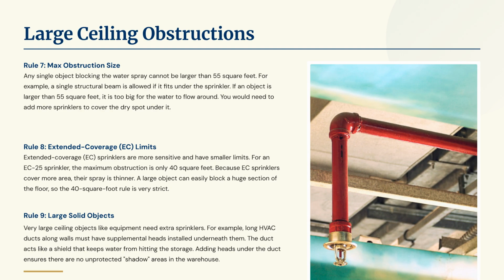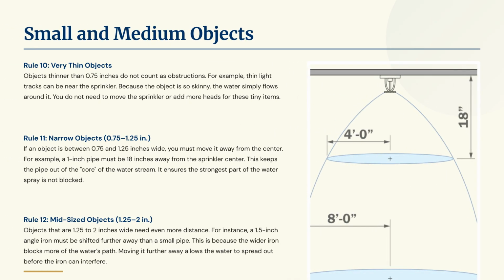Rule 9 requires supplemental heads under large solid objects, like HVAC ducts, to prevent shadowed areas. Rule 10 notes that objects under 0.75 inches are not obstructions. Rule 11 requires narrow objects, 0.75 to 1.25 inches, to be moved 18 inches away. Rule 12 specifies that mid-sized objects, 1.25 to 2 inches wide, need even greater distance.